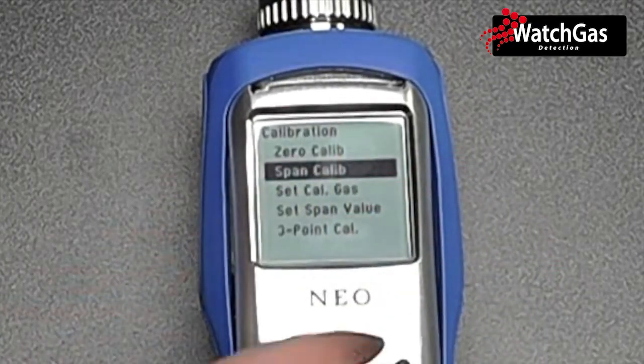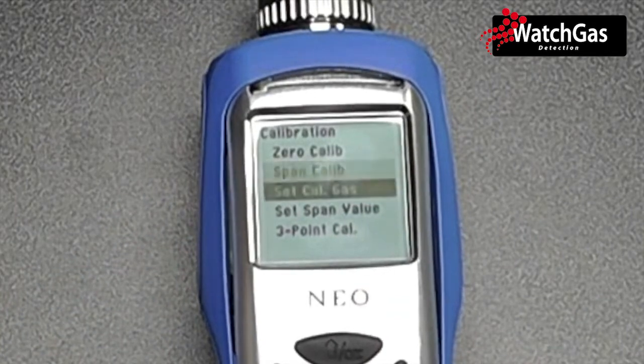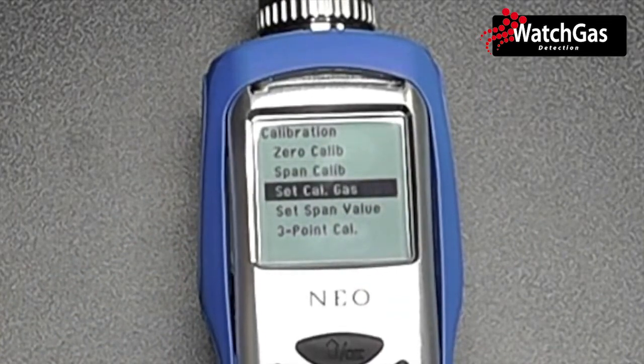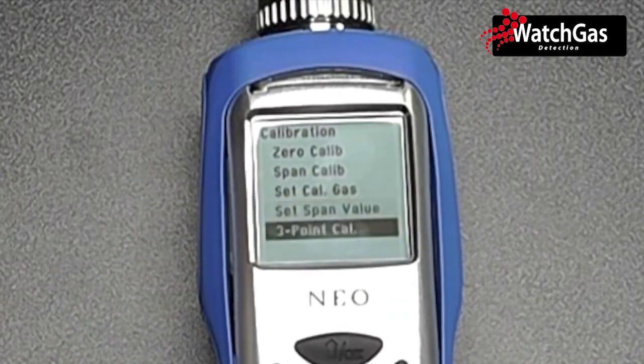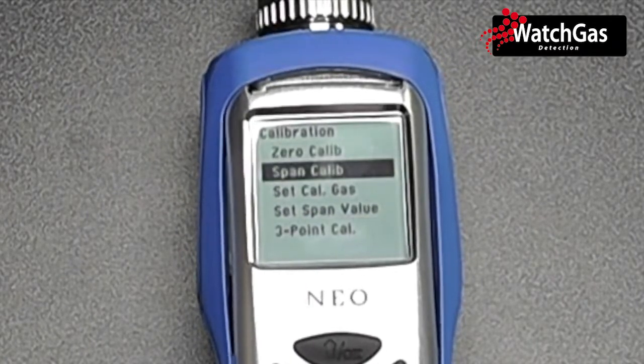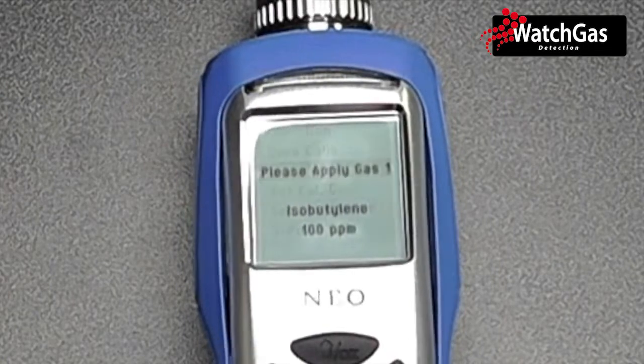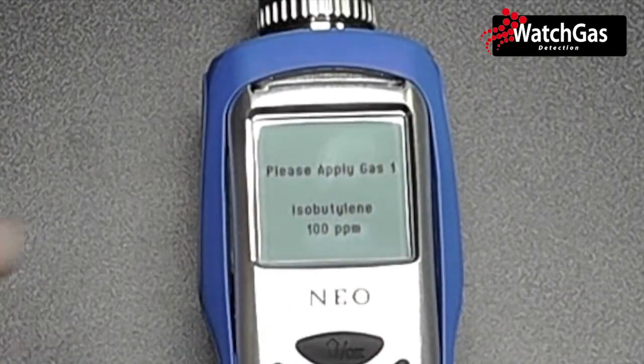we have the option for span calibration. We can set the span cal gas, we can set the span value. We also have the option for a 3-point calibration. So if I want to perform a span calibration, we hit the enter button. It'll then ask me to apply gas 1. This happens to be isobutylene at 100 parts per million.